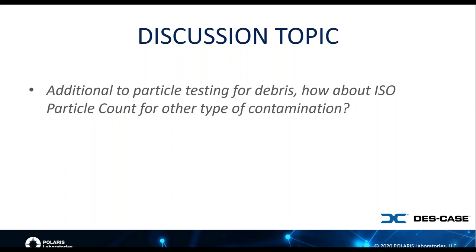Water can show up as a contaminant in a particle count, because it actually scatters the particle count. What I do know, having been through the POLARIS lab, is that you use the ASTM D7647 method, which allows you to actually put soft particles and/or water back into solution in the oil, so it doesn't impact that.